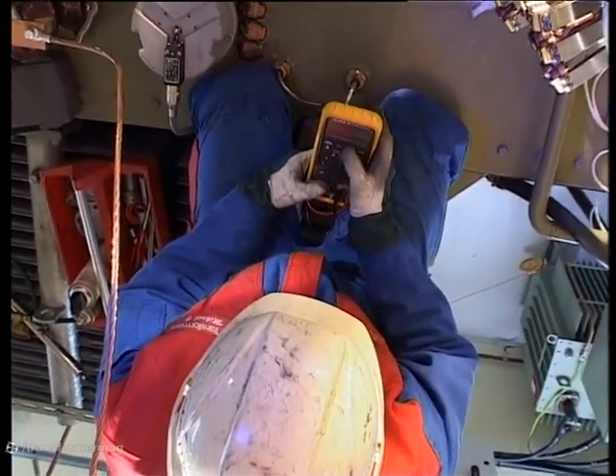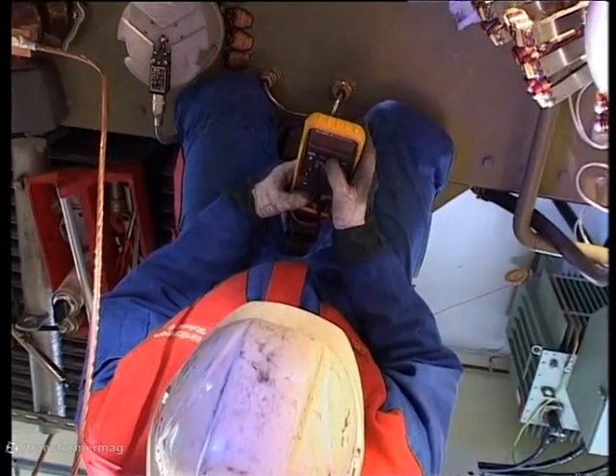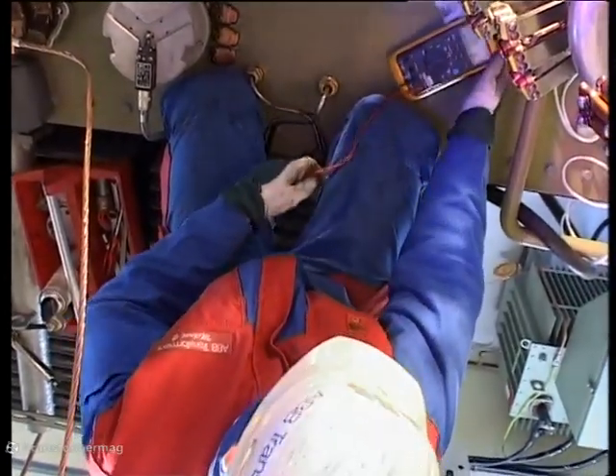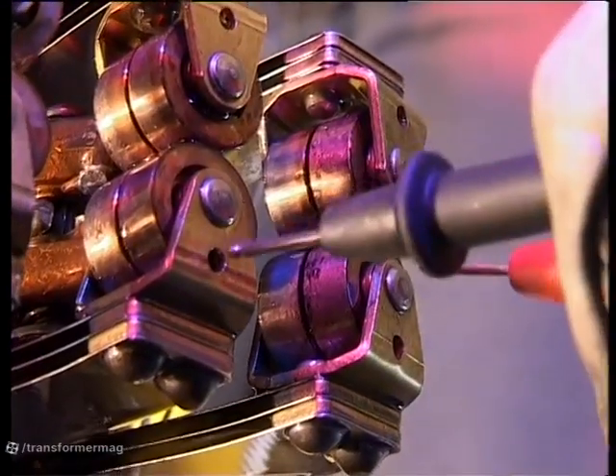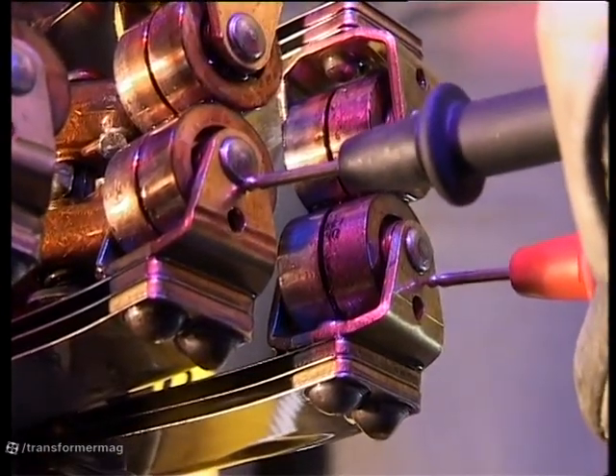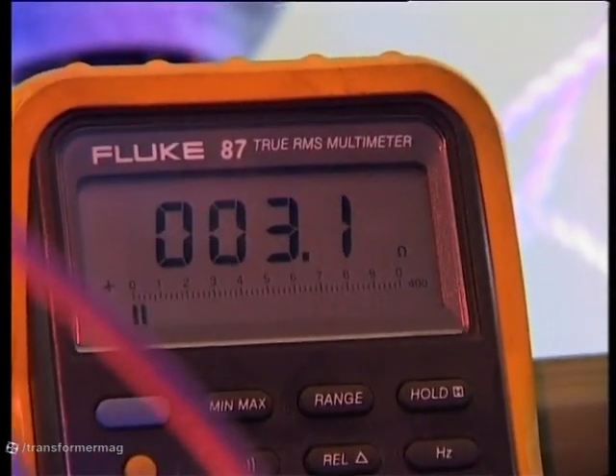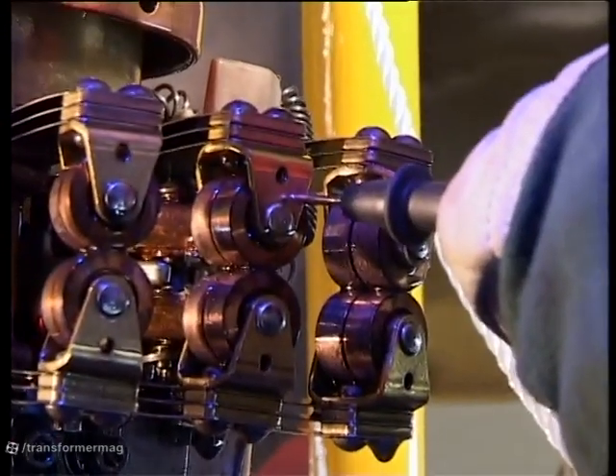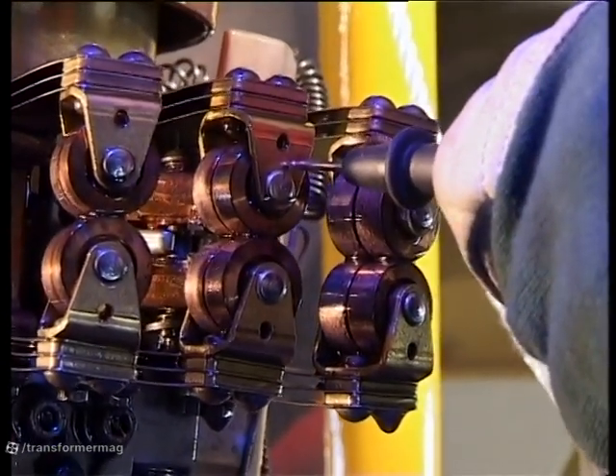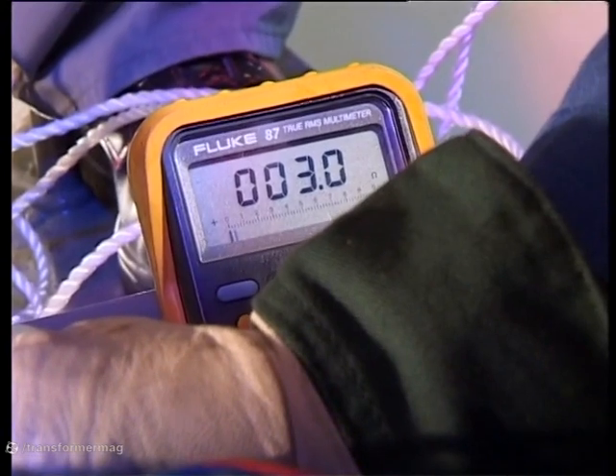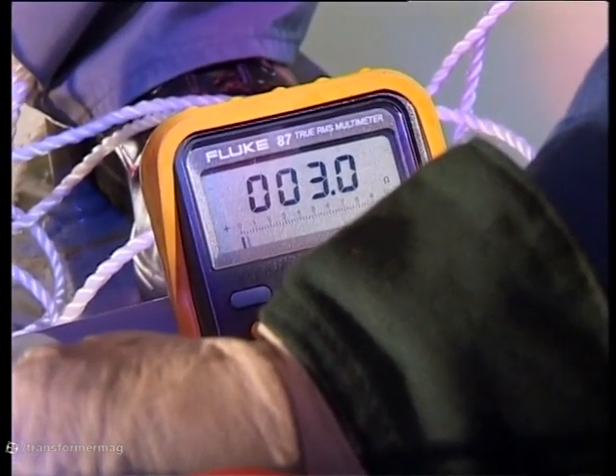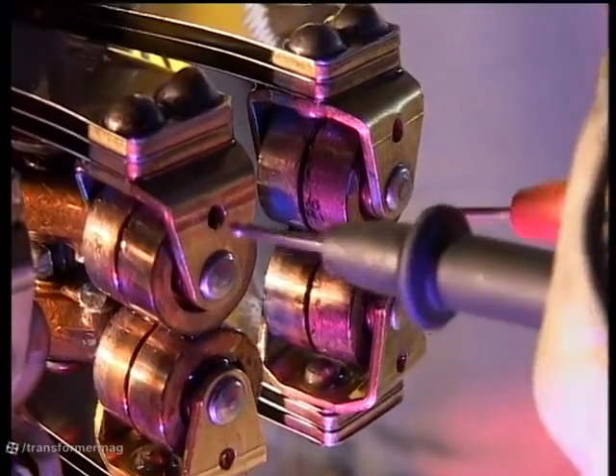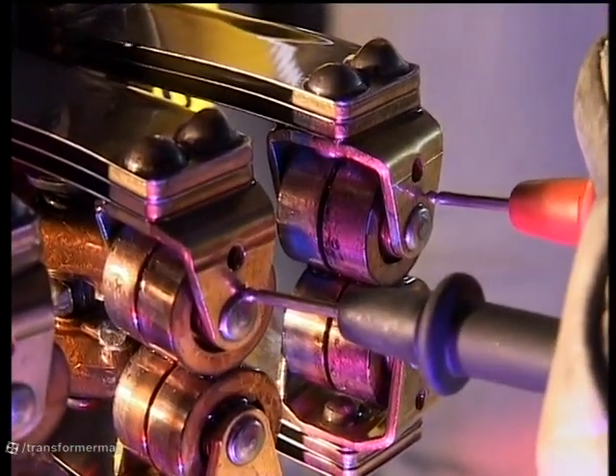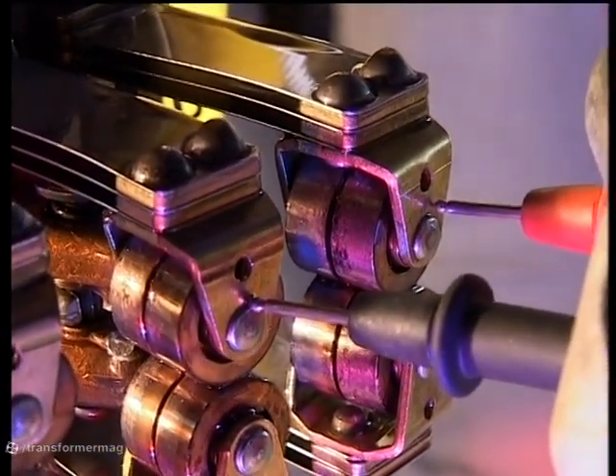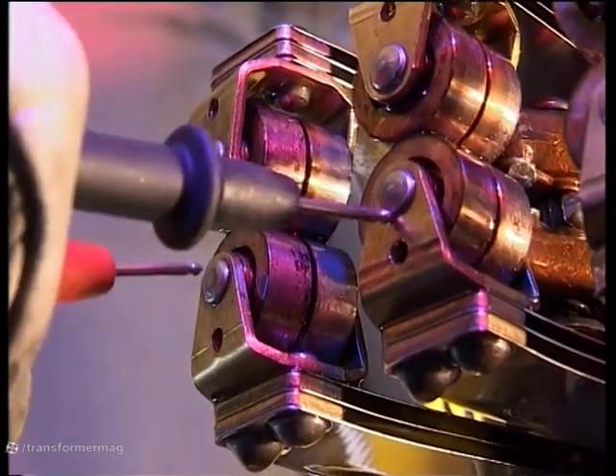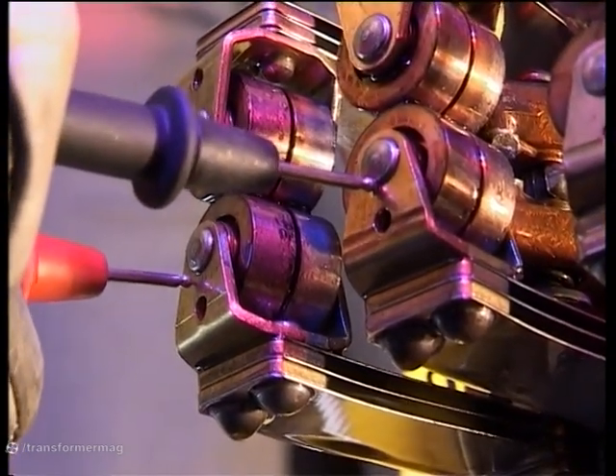To check transition resistors, connect one ohm meter lead to a resistance contact and the other lead to the main contact in a phase. Measure the resistance. Repeat with the other resistance contact and then proceed to the other phases. You can tell whether the resistors are undamaged by comparing the resistance readings. The resistance value for tap changers with CE marking is stated on the rating plate. The readings must not differ by more than 10%.